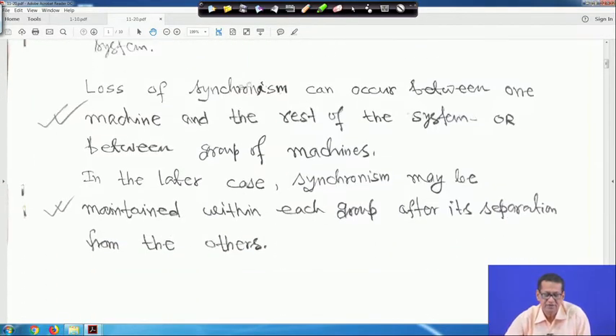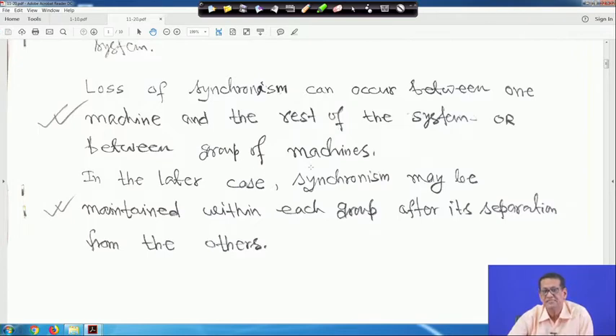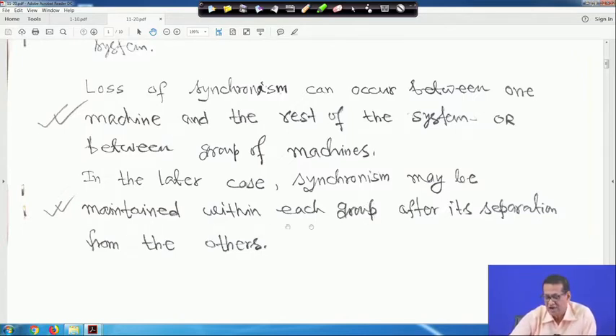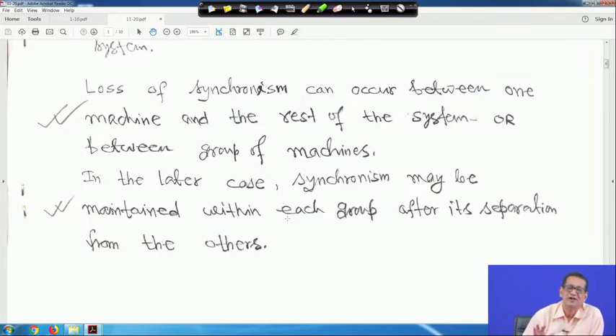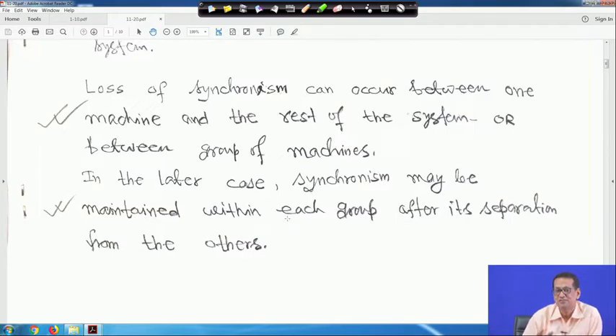Loss of synchronism can occur between one machine and the rest of the system, or between groups of machines. In the latter case, synchronism may be maintained within each group after its separation from the others — if synchronism is lost between two groups, they can be isolated, but machines within one group may not lose synchronism with each other.